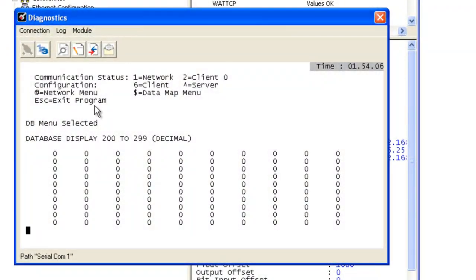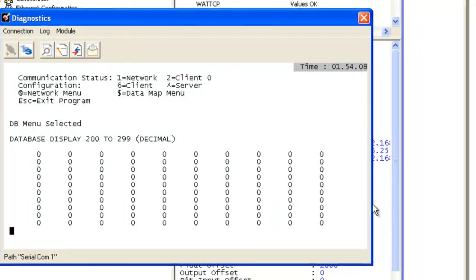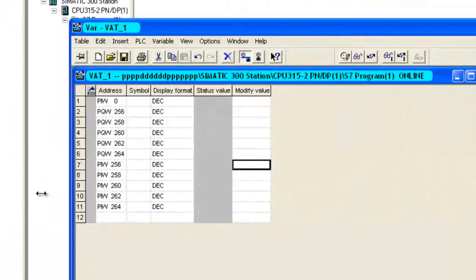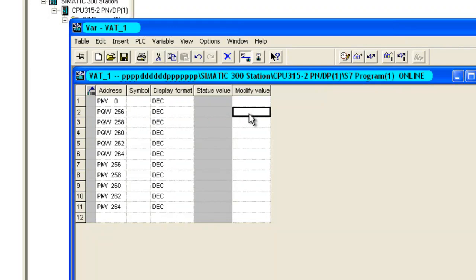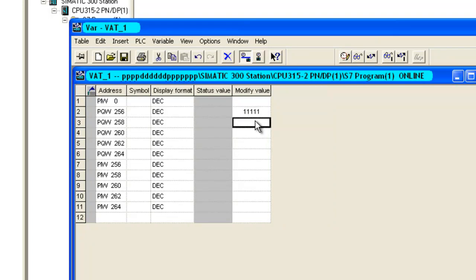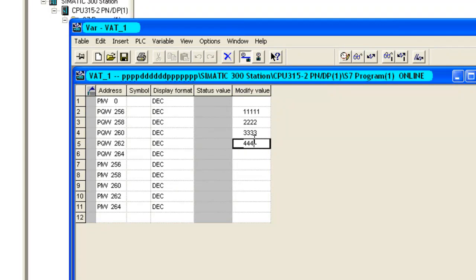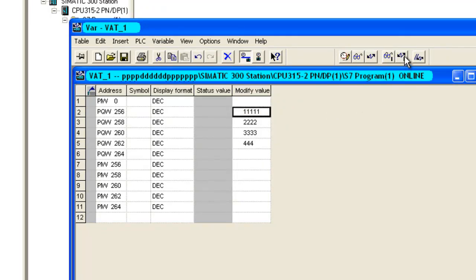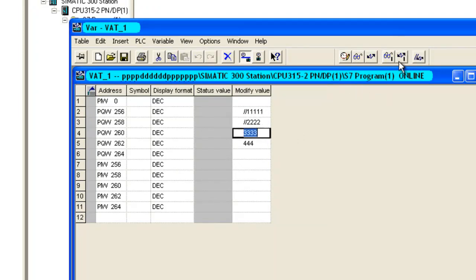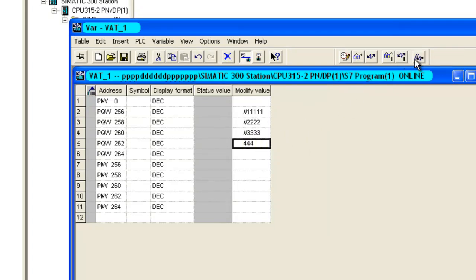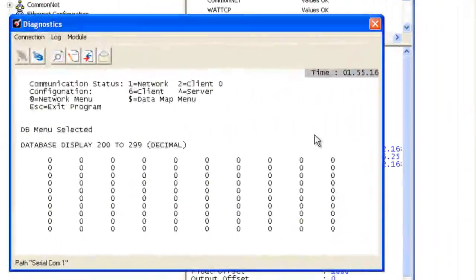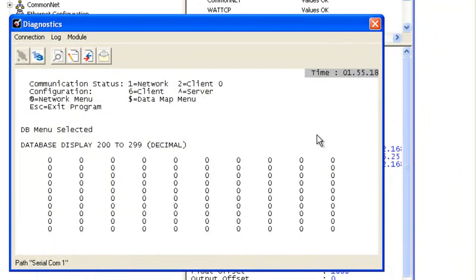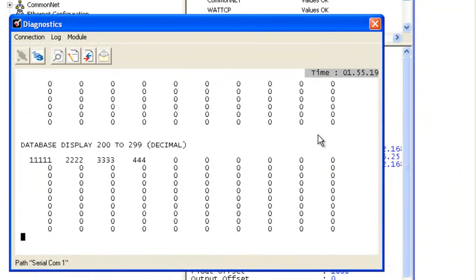Now here we're going to go over to the Step 7 where I've already created a function block to write 4 bytes of data starting at 256. So here we're going to modify this value. We're going to type, we'll just type 1's. On this next one we'll just type some 2's, 3 and 4. Because I don't have logic pushing these values out to the Profibus side, we're going to have to manually force them. So here we're forcing all these values to go to the ProLinx. And that's the last one. And now we'll go back over to the diagnostics and type S to refresh the memory. And there you are, you have all the data.